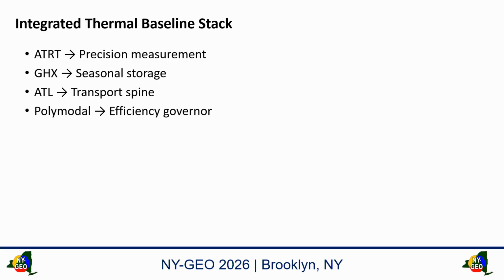All right. The ambient temperature loop is a transport spine. It's just pumping water around. And like I said, that 4,200 tons on that one university, we're pumping that loop with 8 horsepower. So you can take 4,200 tons times 3, that's the gallons per minute. We're doing that with 8 horsepower. Yeah, that's pretty amazing. And because we're operating off a temperature differential, not a pressure differential. All right. Next, we go into the polymodal mode, and those are the efficiency governors that connect to these systems.